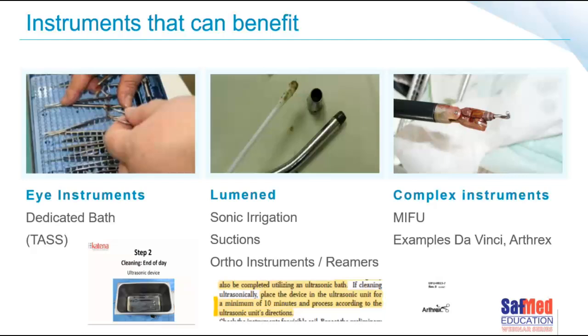Remember now, when a manufacturer makes an instrument, they are obligated, it's part of the legal requirement, that they take the instrument, they inoculate it with a known amount of contaminant or microorganism, and they put it through some cleaning steps, and at the end of the day, they have to be able to prove to you that if you follow those correct cleaning steps, this device will now be clean. Very important to follow those cleaning steps, because if you're not following them, you do not know for sure that you have now a clean instrument. And a lot of instructions for use, in fact, will stipulate that the device needs to go into an ultrasonic bath.